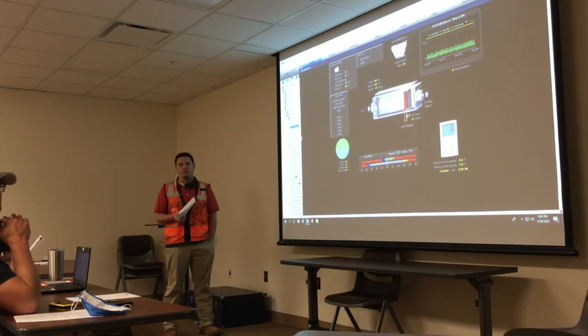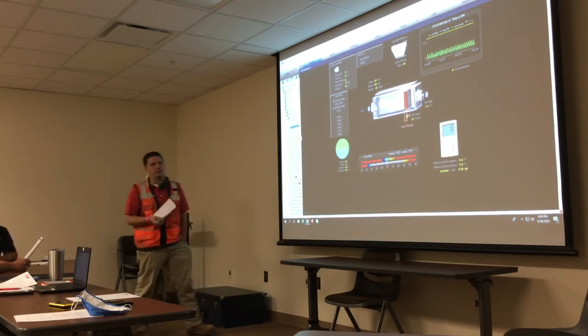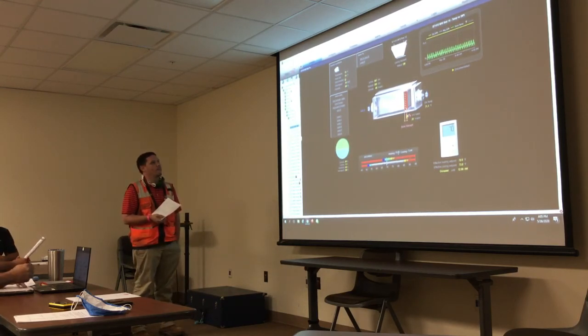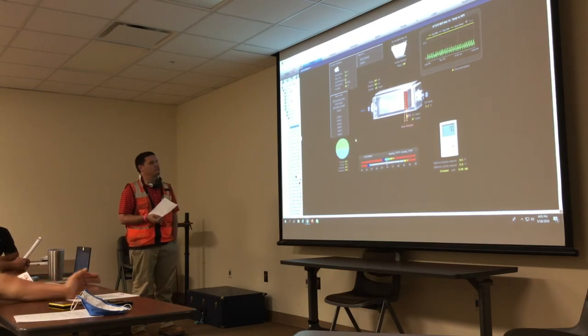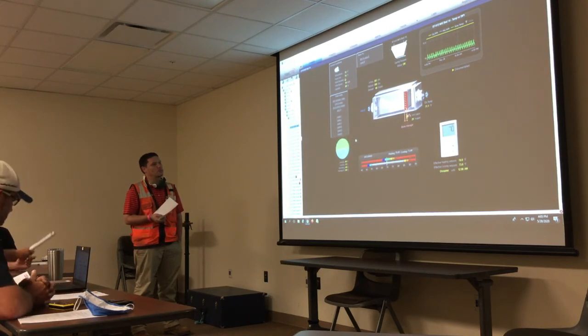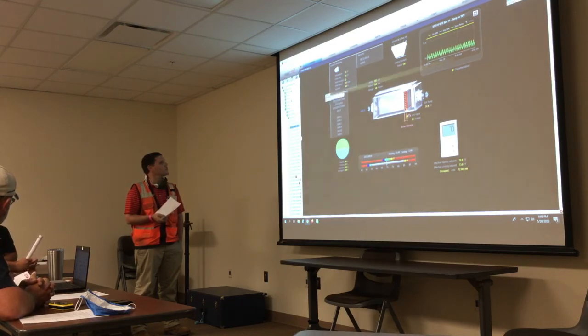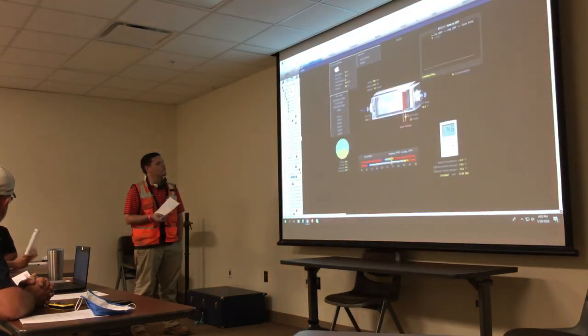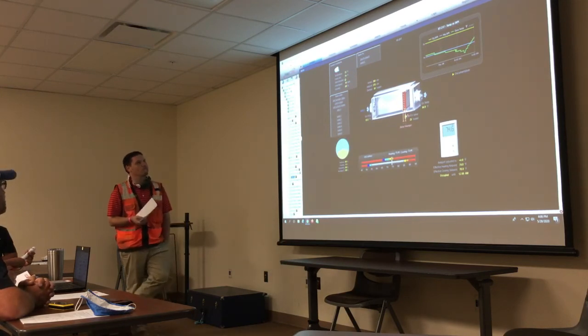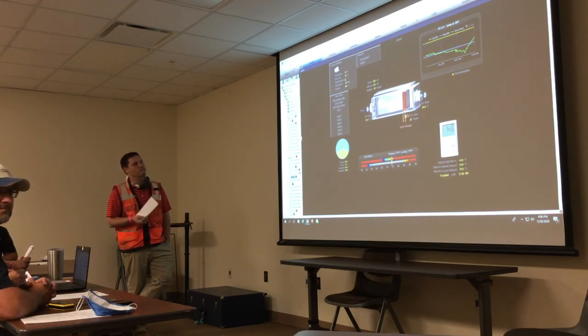Well, what's confusing to me, and I'll just maybe jump on one of these patient rooms, just real quick, Joe. Yes, sir. You're going to expand on training here. So for instance, pull up 217 and look at the trend. Temperature versus set point trend. Now you see the green bars just going all over the place. The yellow stays the same. The yellow is the set point. Right. So yellow's 76. We're riding around 74, and then we drop down to 73, and then 73.7, all the way down to 72.9, and then it starts warming back up.